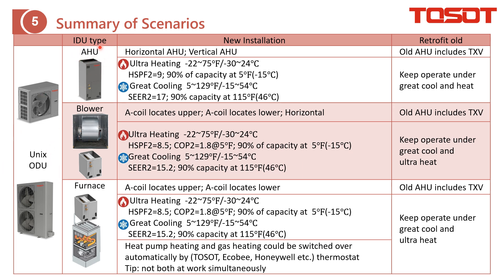The AHU can be from TOSOT or from any other brands. For TOSOT, we support horizontal and vertical installation. With this setup, you can achieve ultra heating down to minus 30°C, and you can also do great cooling. This is for new installations. For retrofit projects using an AHU not from Trane, we only require that the AHU includes a TXV. The purpose of the TXV is to do the metering in cooling mode.